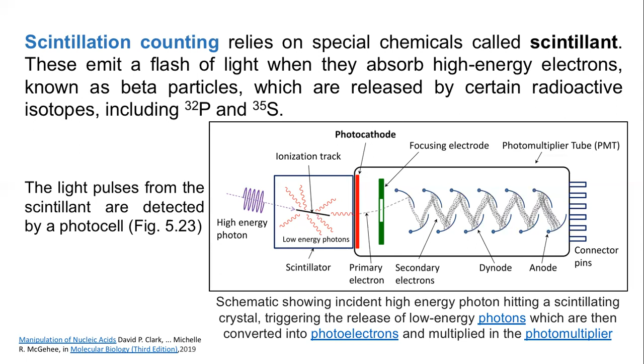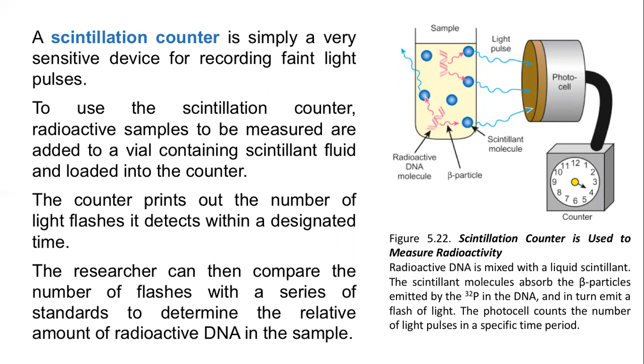As you can see here, this is your sample, and here you can see DNA with radioactive labeling, and this is your scintillator. In this case, this is the liquid scintillation system, where you have your sample in liquid form. Once the beta particle is emitted, it will give a flash of light, as you can see here, a light pulse. These light pulses are then transferred into the photomultiplier tube or the photocell, which will detect it. Finally, on the counter, you can see the count of the photons being emitted for a particular period of time. So this is how it works.